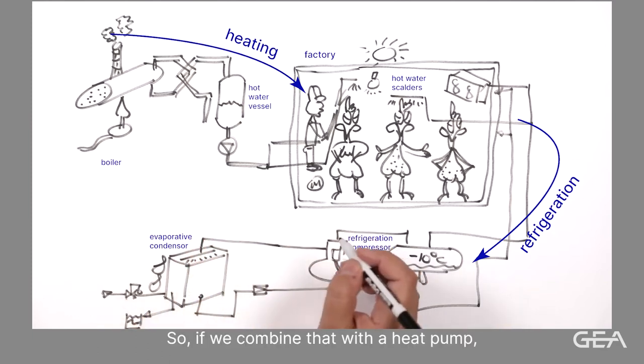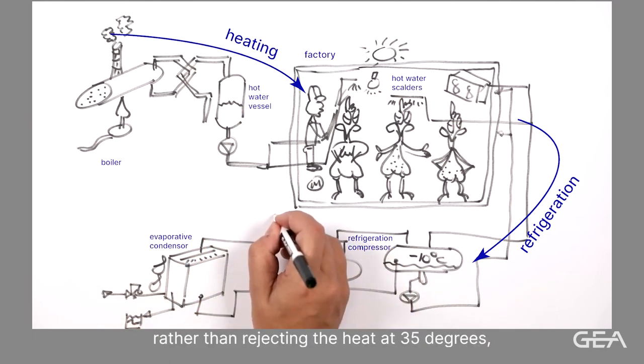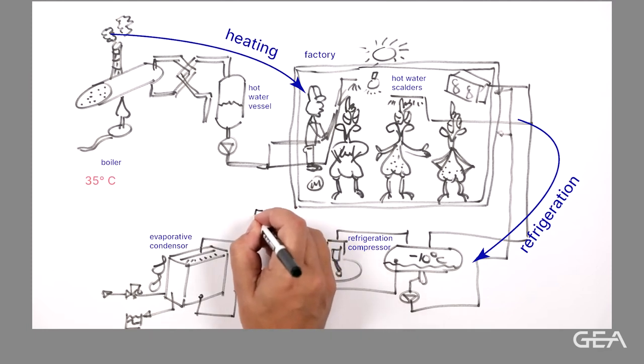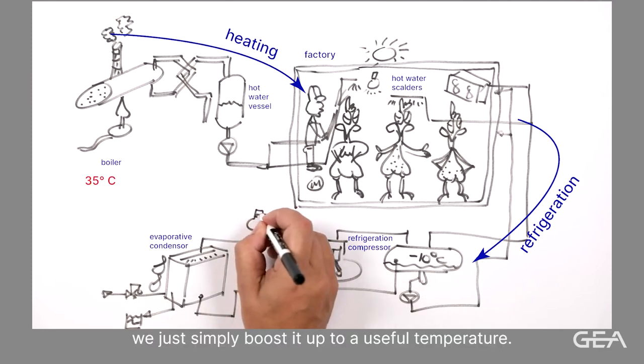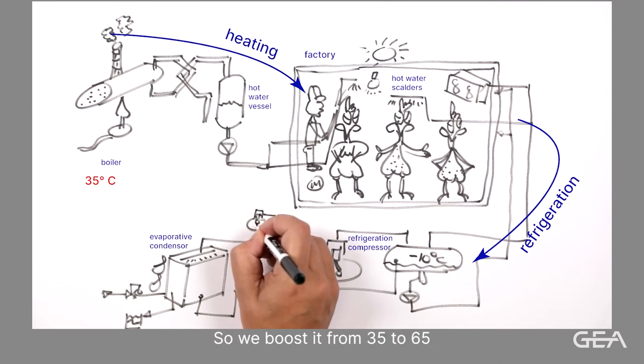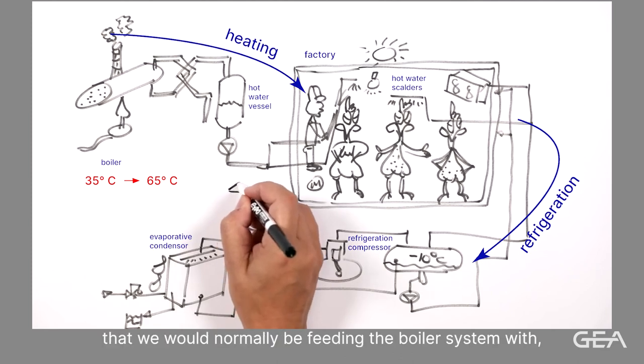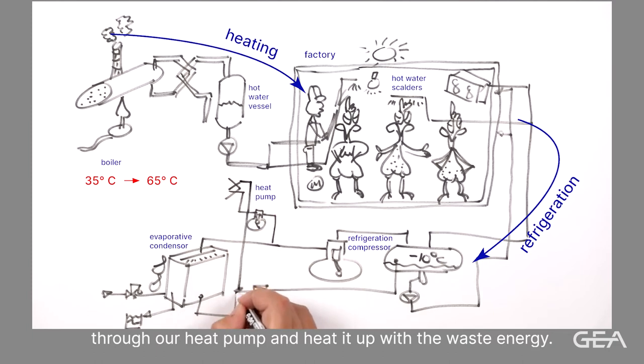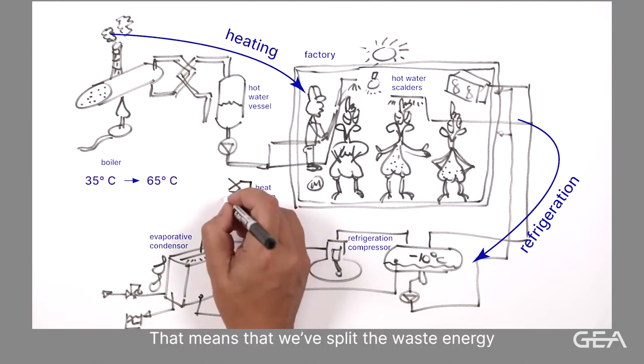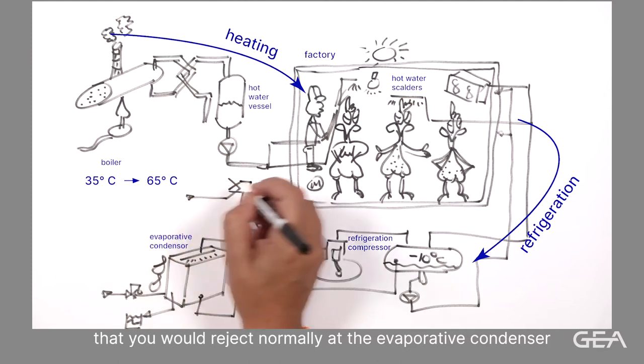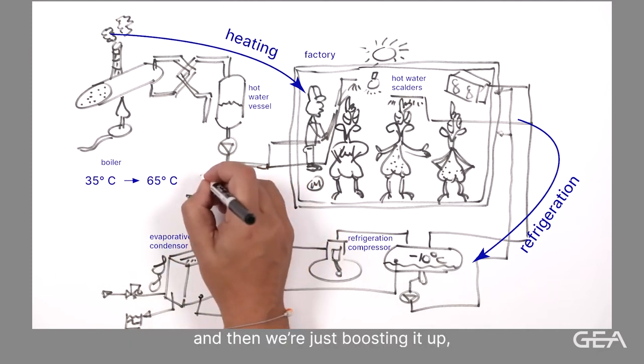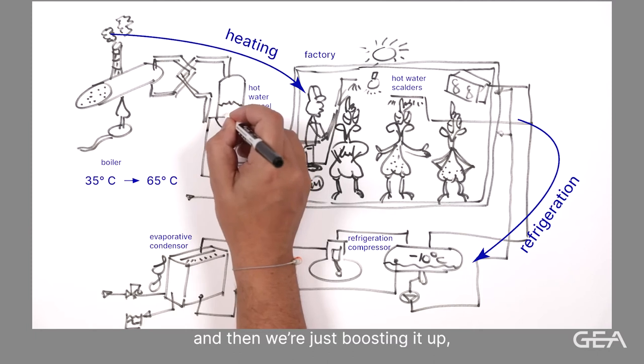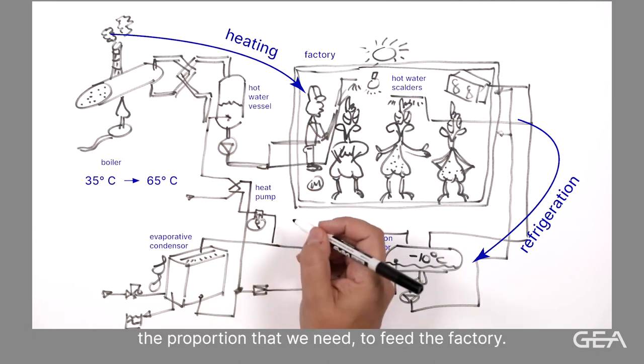So if we combine that with a heat pump, rather than rejecting the heat at 35 degrees, we just simply boost it up to a useful temperature. So we boost it from 35 to 65. And then we use the cold water that you would normally be feeding the boiler system with through our heat pump and heat it up with the waste energy. Which means that we've split the waste energy that you would reject normally at the evaporative condenser, and then we're just boosting it up the proportion that we need to feed the factory.